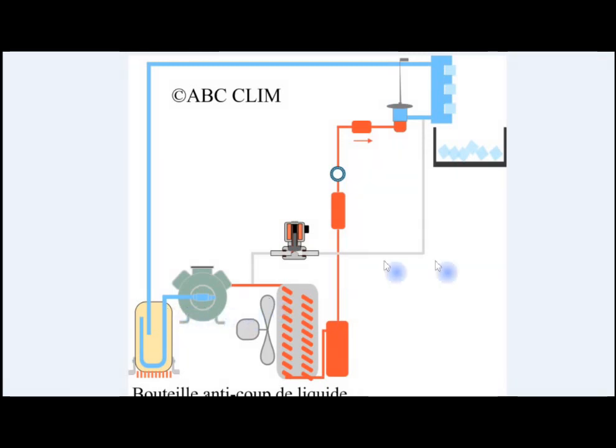However, when we want to defrost an evaporator or remove the ice, we need to feed this electric valve which is directly connected to the expansion valve, just after it. Once powered, the gas will go directly into the evaporator. It cannot return in this direction since here we have a check valve. The gas will heat the evaporator and the ice will fall into the storage.